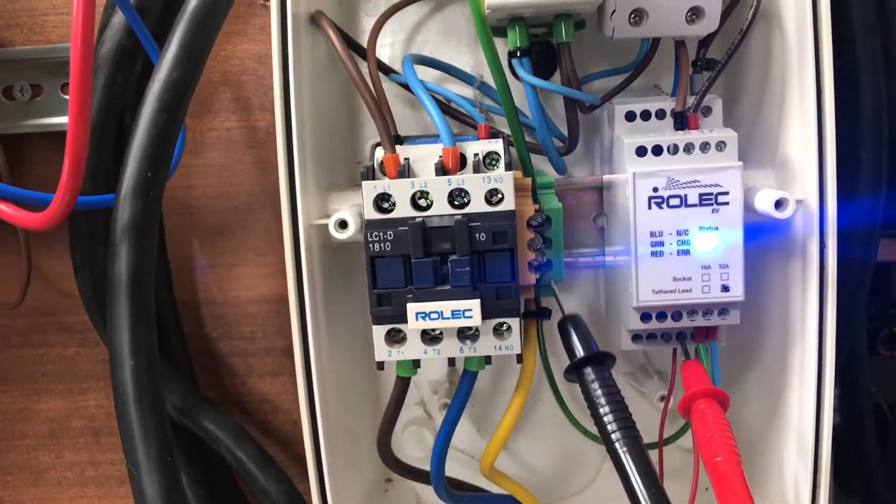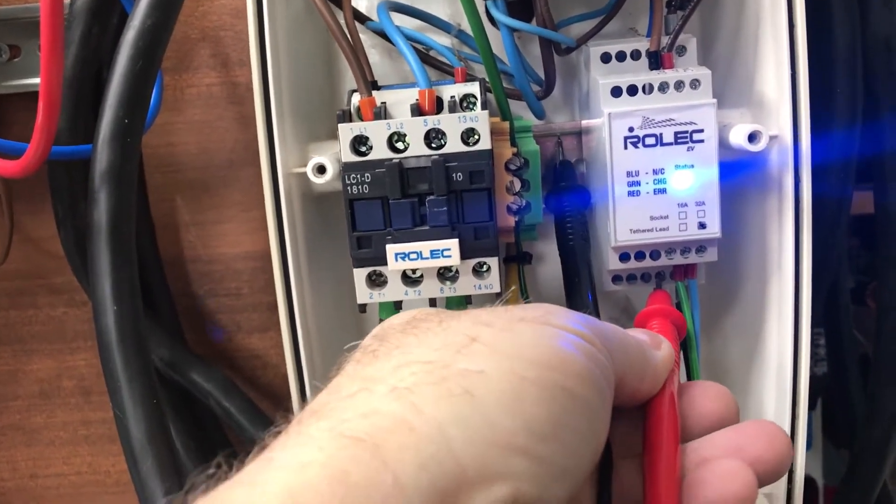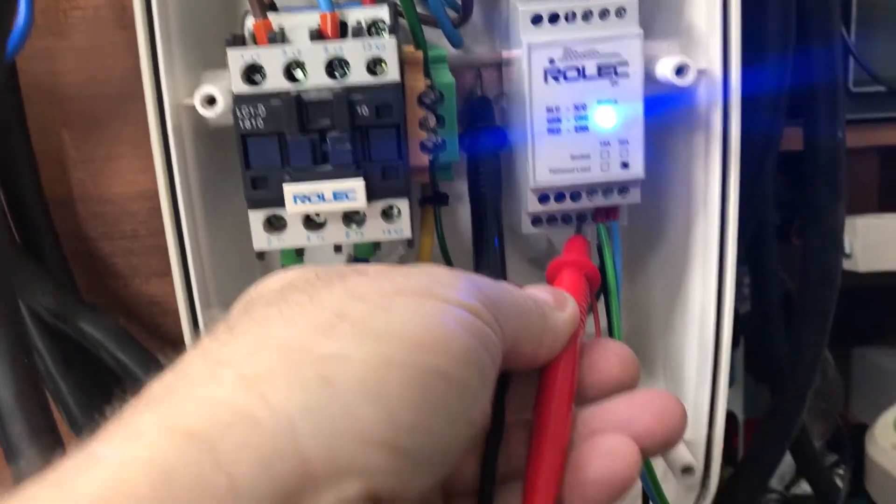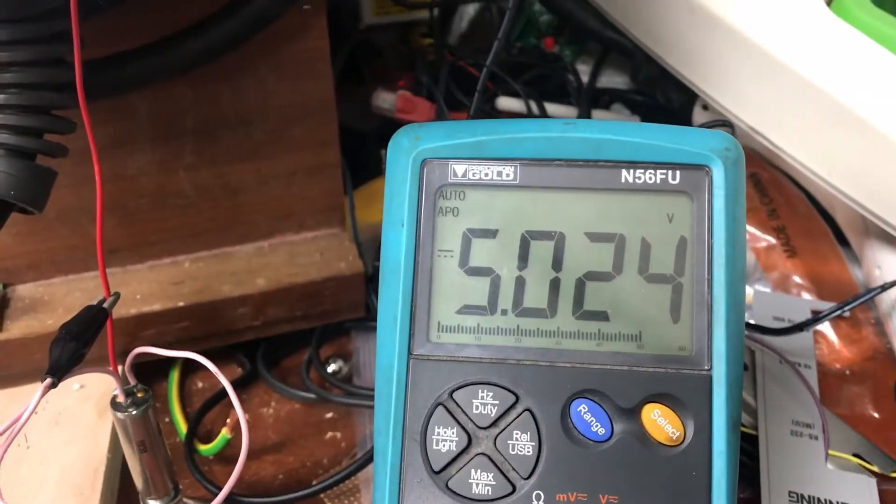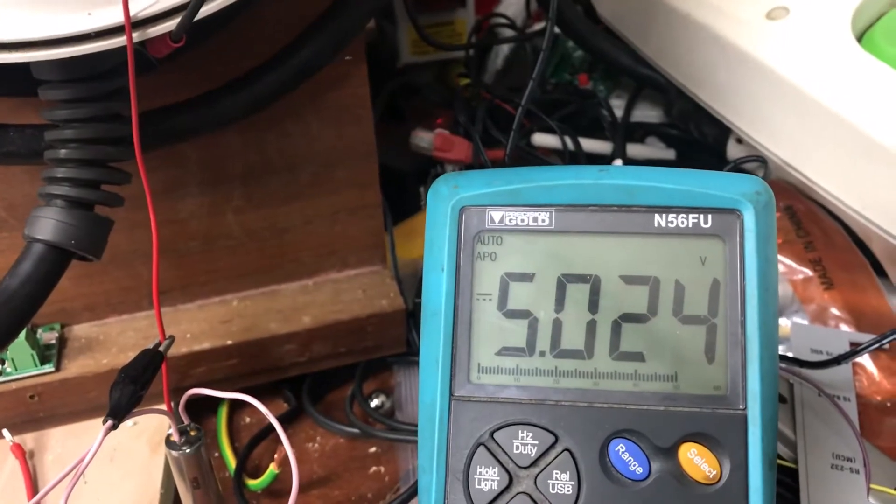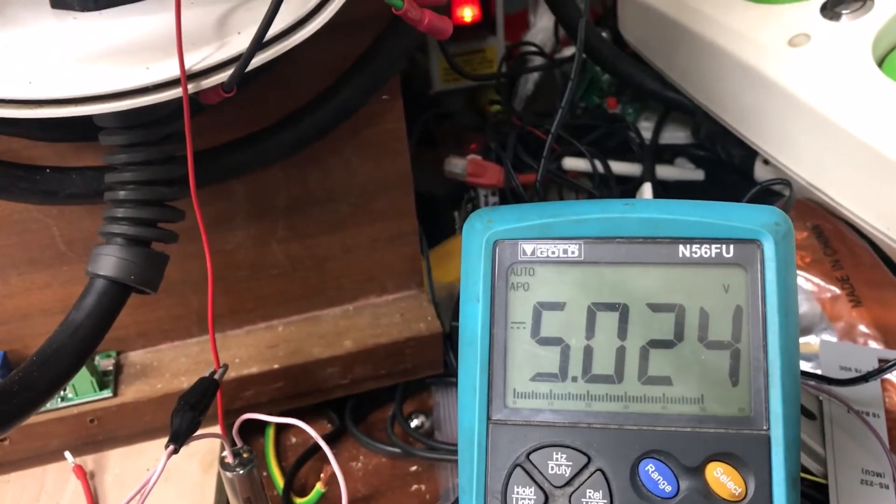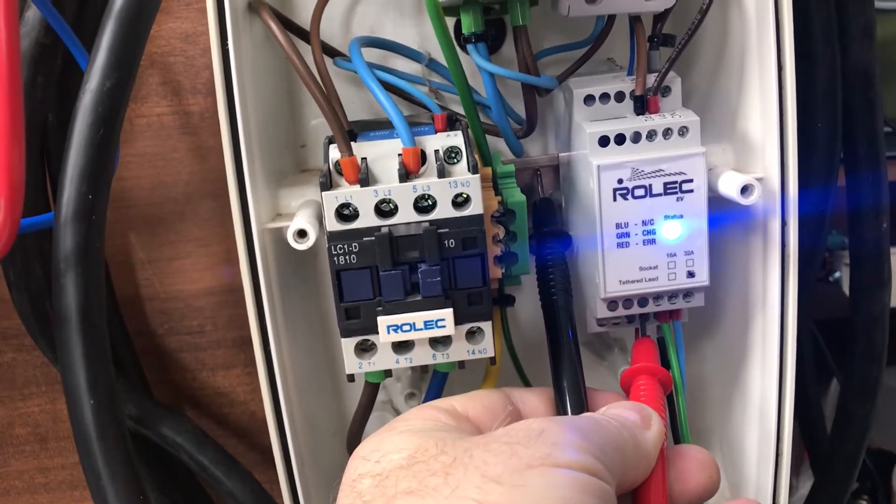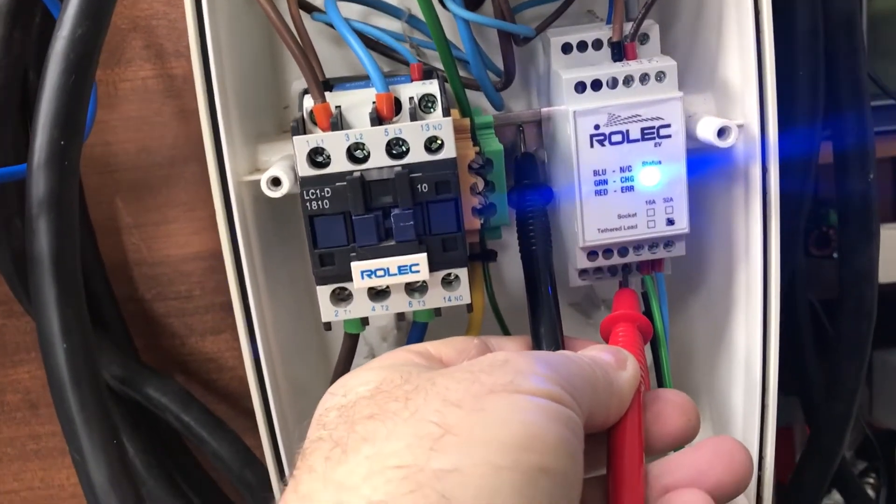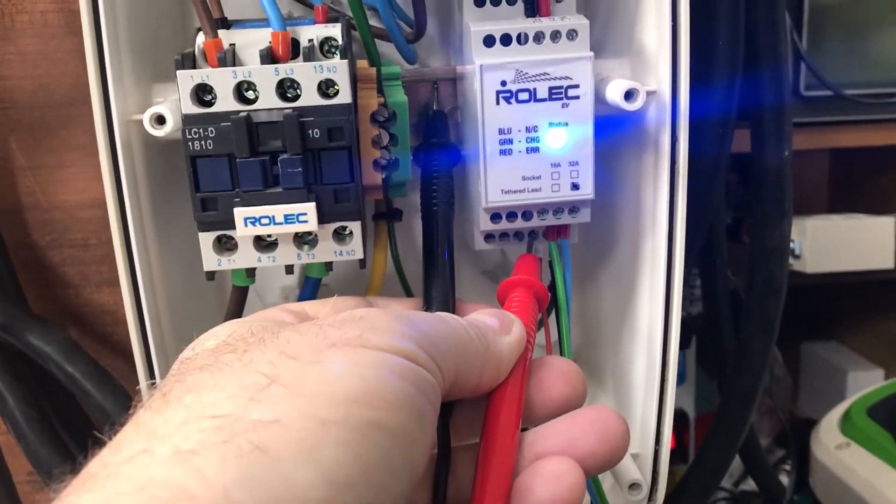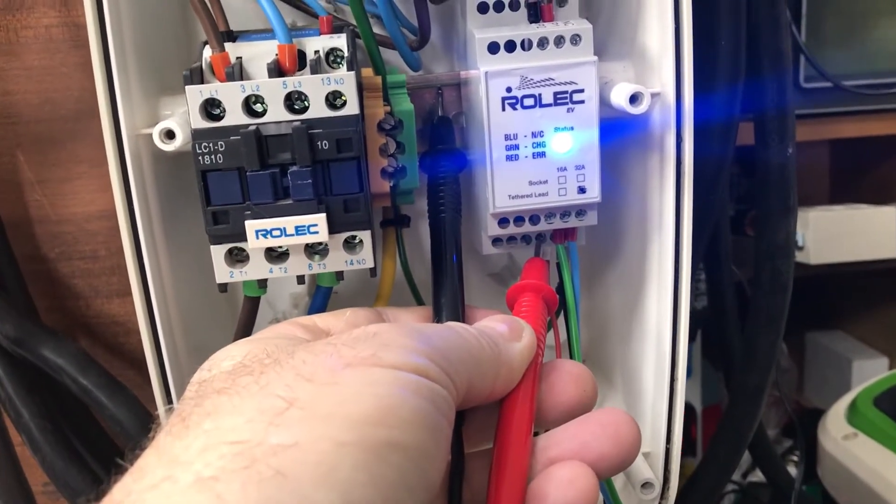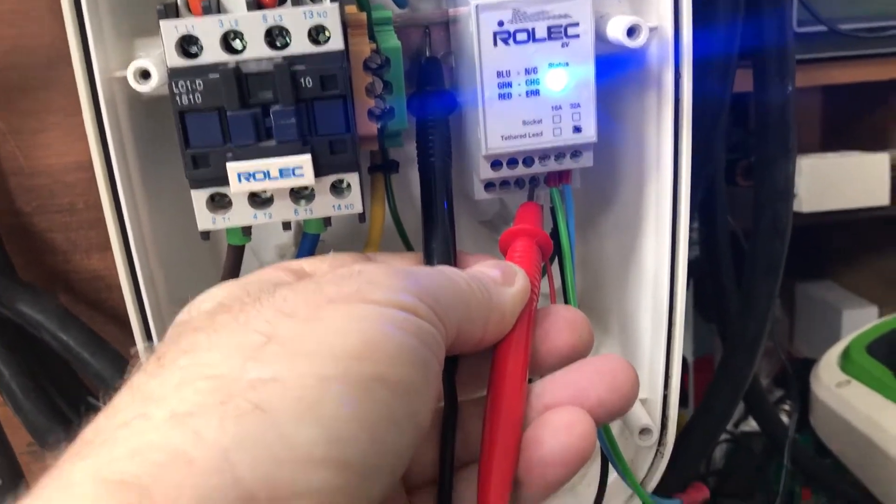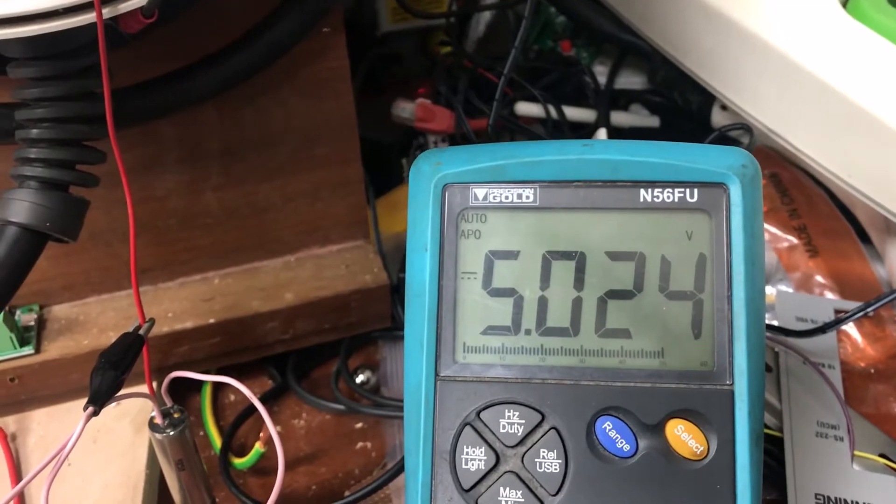I'm basically putting my multimeter there, and if we look at the multimeter, it's telling us we've got 5 volts DC, which I'm happy with. It's always advisable to do these sort of checks. This is live, you have got 240 volts around. I would not expect to see 240 volts on that pin, but believe me, I've been caught out in the past where sometimes these pins can float at mains voltage. So it's a quick little check just to prove to yourself that what you're playing with is low voltage.